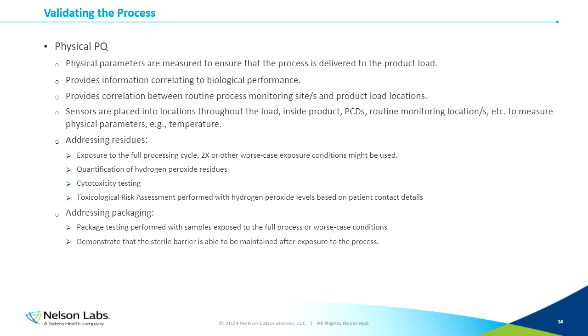This provides correlation between routine process monitoring sites and product load locations. If we have selected a routine process monitoring site, we need to see how that relates to performance inside the load. And physical performance qualification allows us to do that by measuring those parameters at those various sites. We place sensors into locations throughout the load inside product, and if being used, process challenge devices, routine monitoring locations, et cetera, to measure physical parameters. An example of that would be temperature.